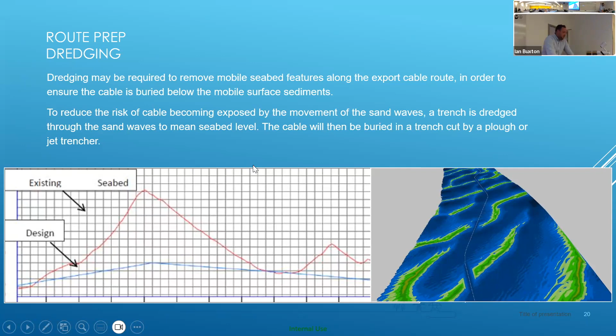You have to remove the seabed features along the export route and make sure the cable is buried safely, reducing the risk of it becoming exposed by the movement of the sand waves, dredging a trench through the sand waves down to mean seabed level. We then bury the cable in the seabed using a plough or trencher.